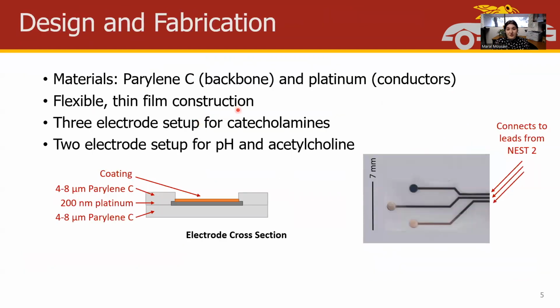The fabrication of these sensors utilizes parylene C as a flexible material and platinum electrodes as conductive leads. These are thin, flexible sensors that will cause minimal scarring of tissue and are highly biocompatible. We have a 3-electrode setup, which is common for electrochemical measurements for catecholamines, and we use a 2-electrode setup for pH and acetylcholine. So the active part of the sensor is shown in this image, and then they'll be connected to leads developed in different nests of the project.